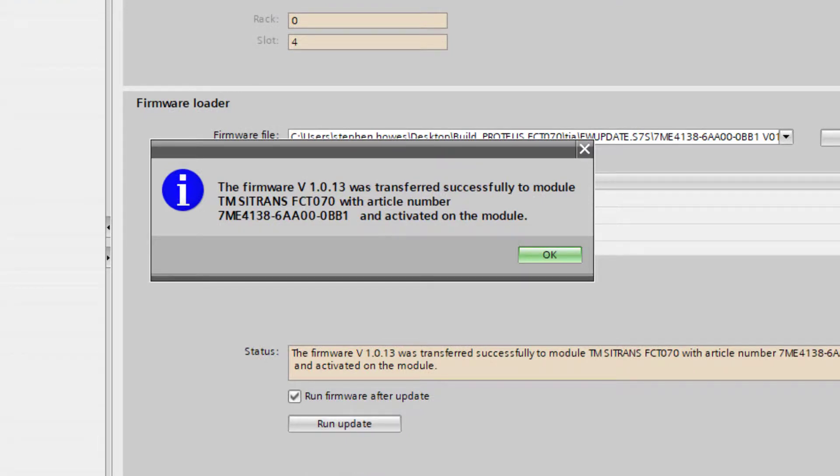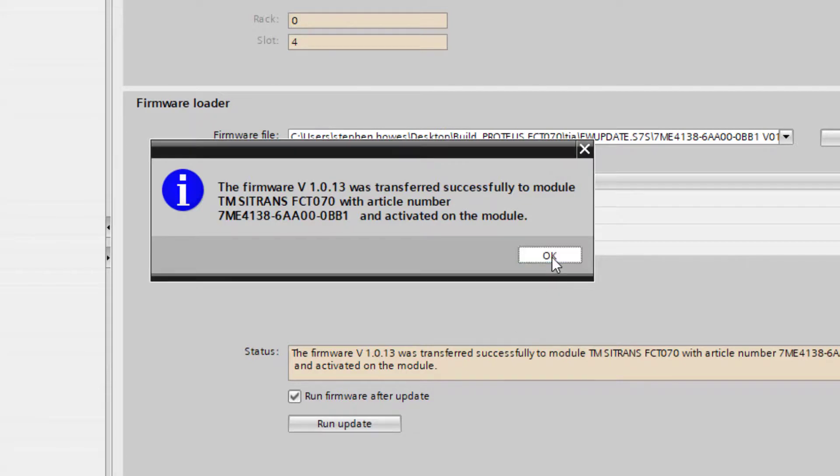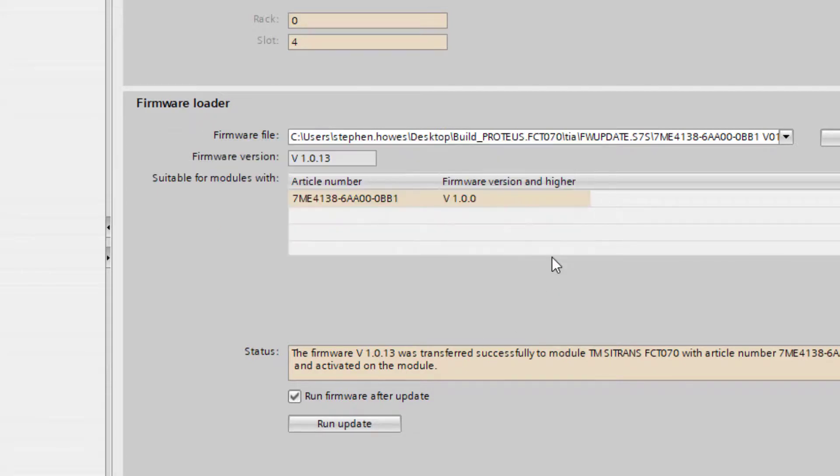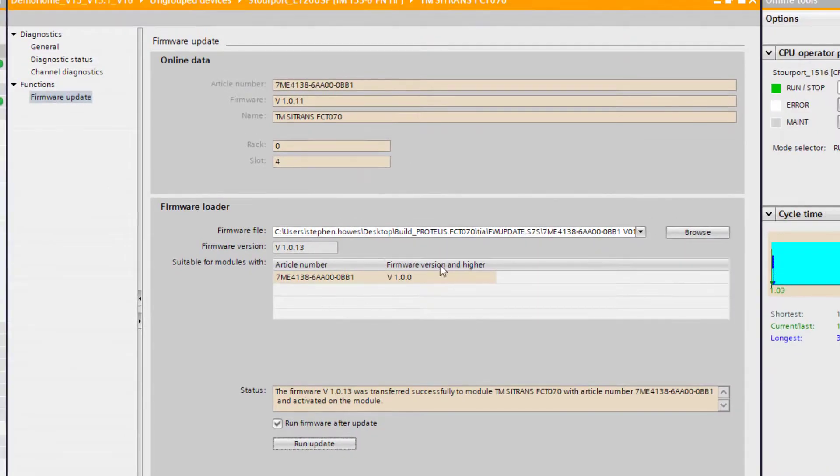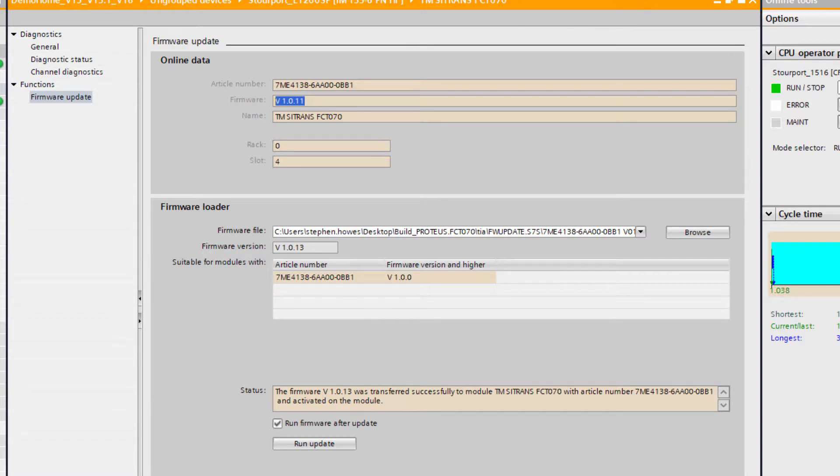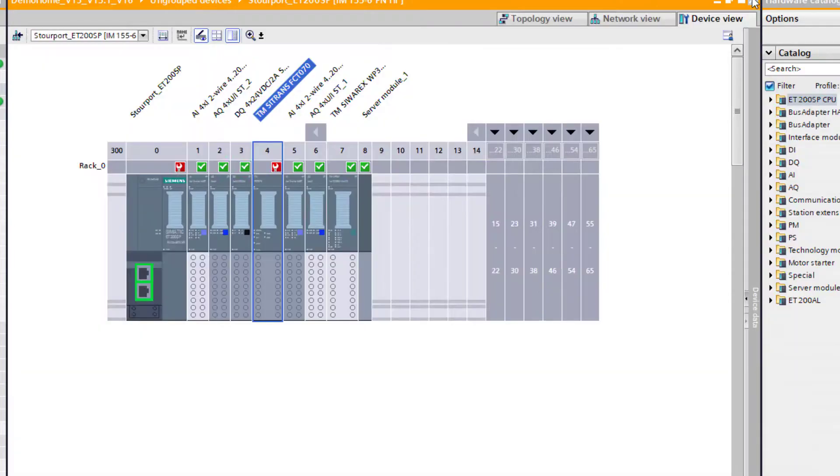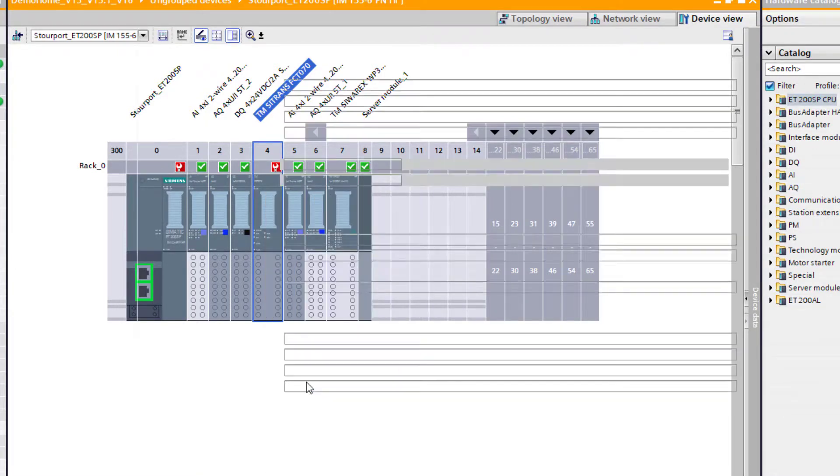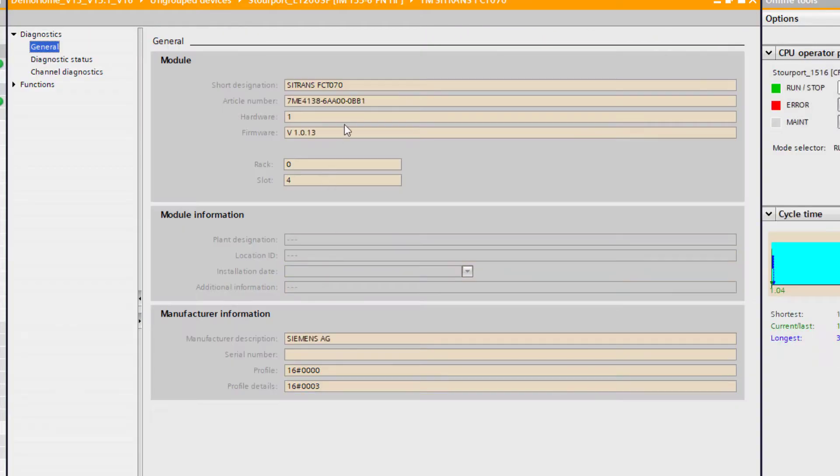So as you can see the firmware is transferred to the module so I'm just going to start the module now. As you'll see from this screen here it's not dynamically updated so you need to come out and then go back in and you'll see there's your new firmware. So that's how you update the majority of IO cards on TIA Portal.